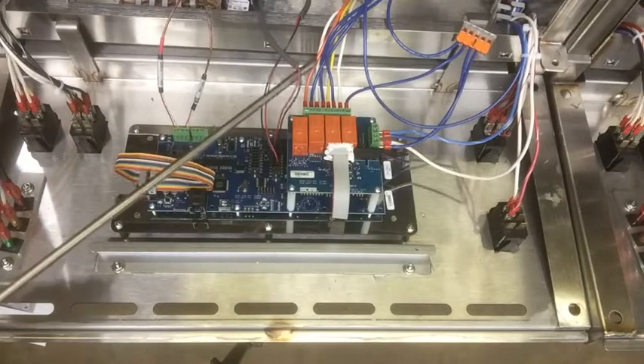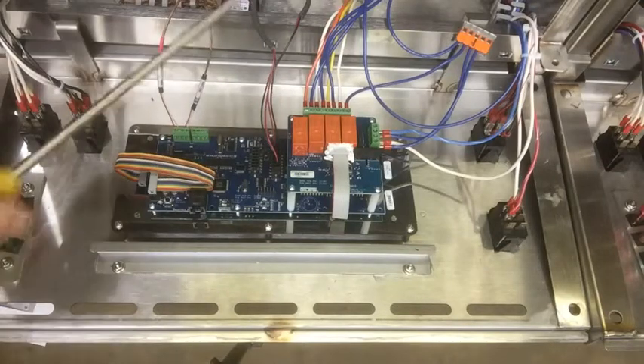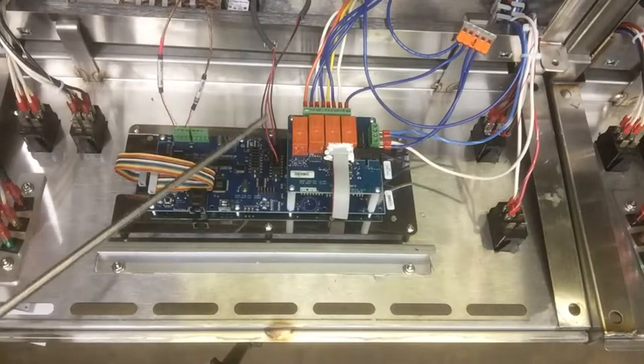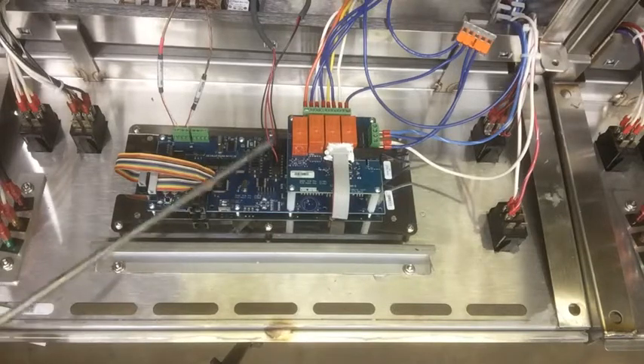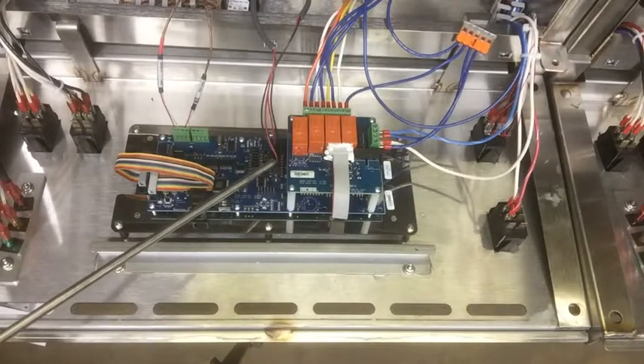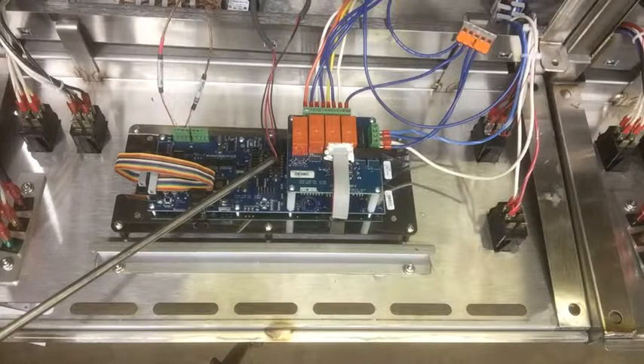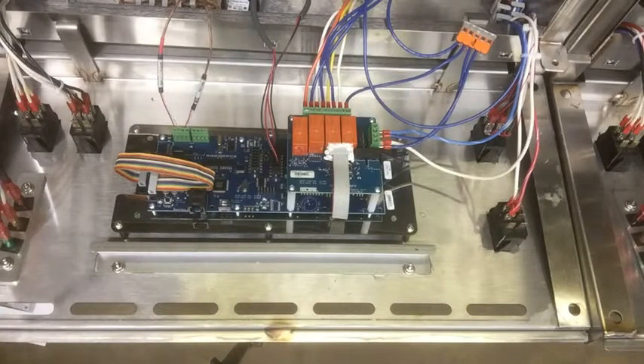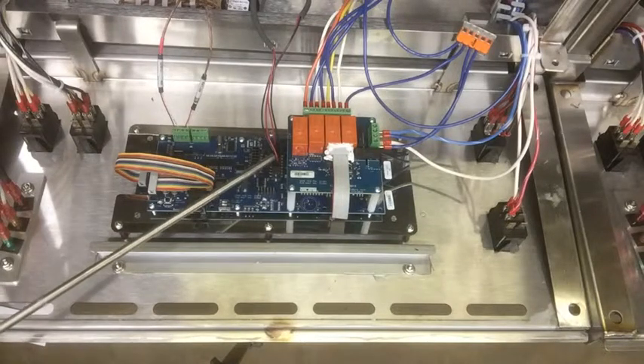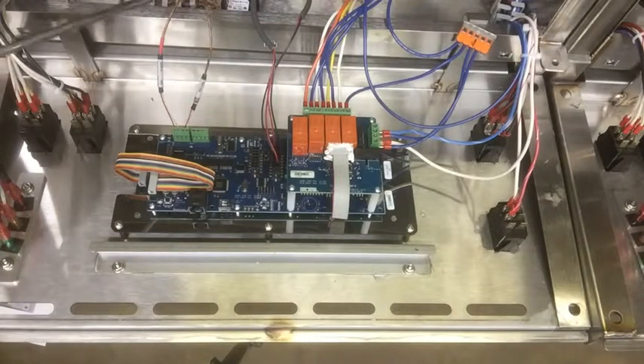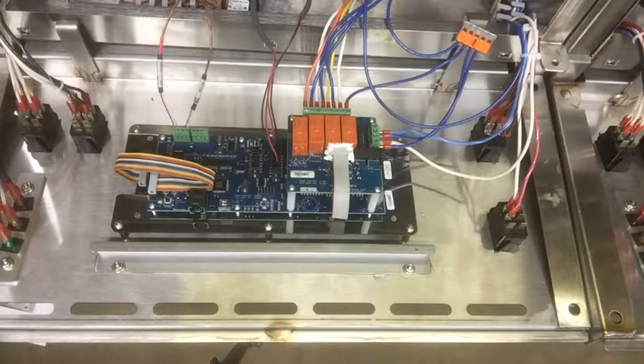Power is coming through right here. This is your 20 to 24 volts coming from your transformer, and it comes into the board right here. On the opposite end of that 16-pin plug, you'll find your drain switch input. The drain switch is wired normally open, and the controller is looking for a closed output in order to heat. If it sees an open output, from your drain switch or an open input into the board, it's going to sound your alarm and send up a message that says drain open.